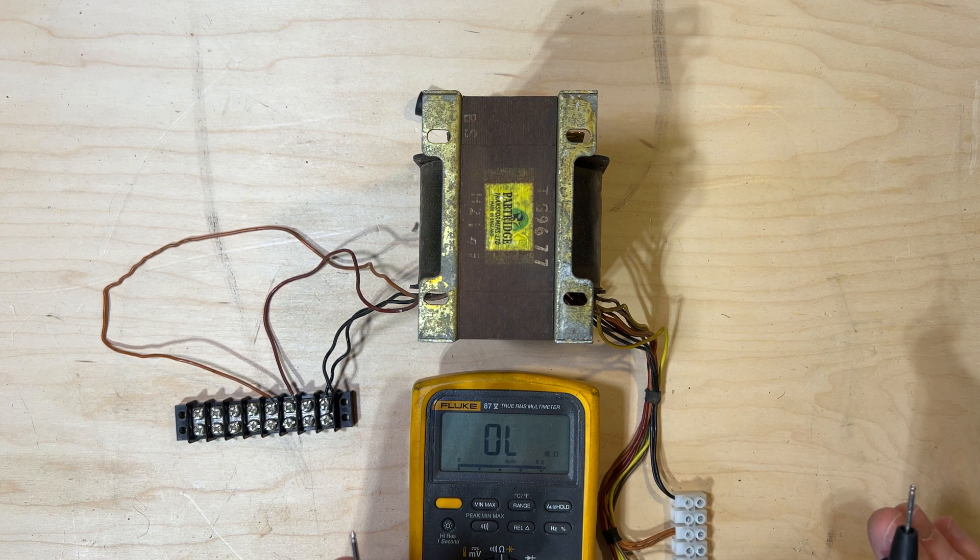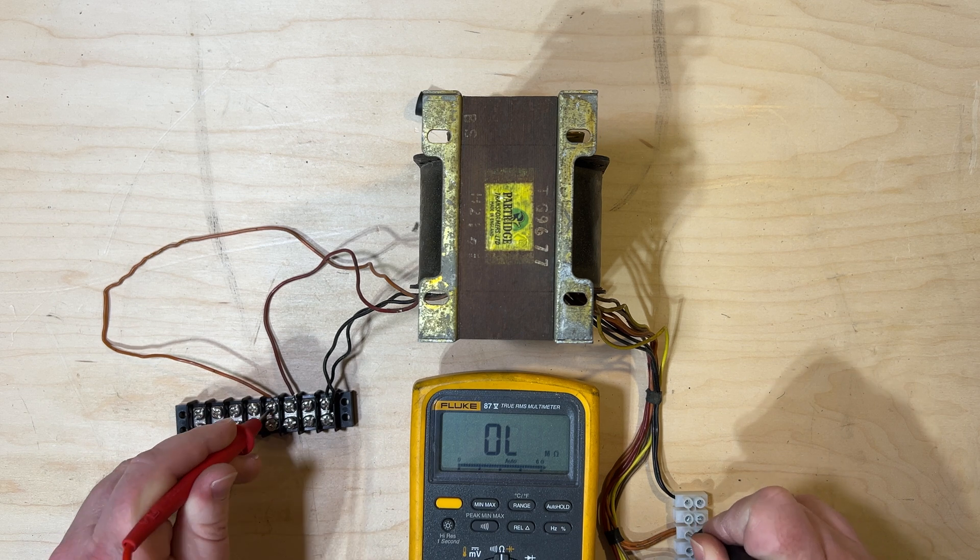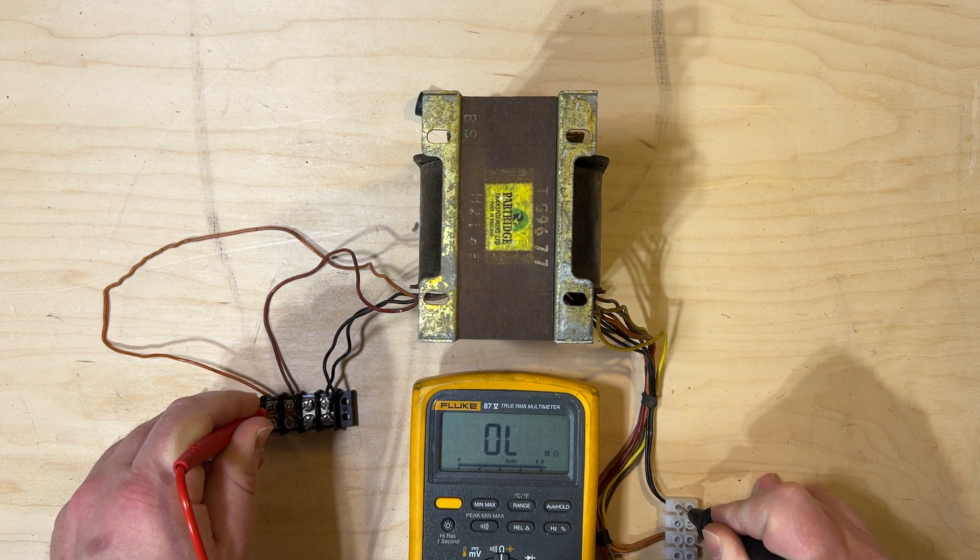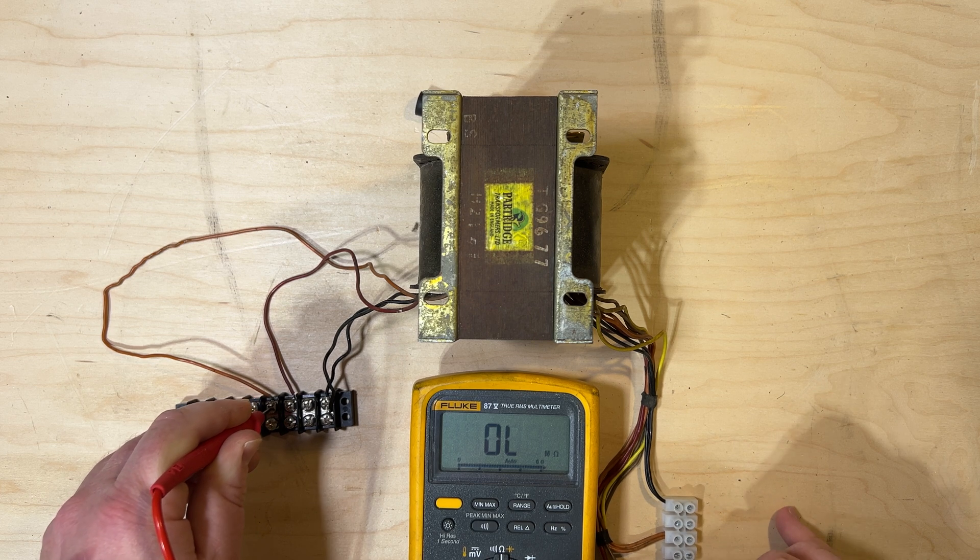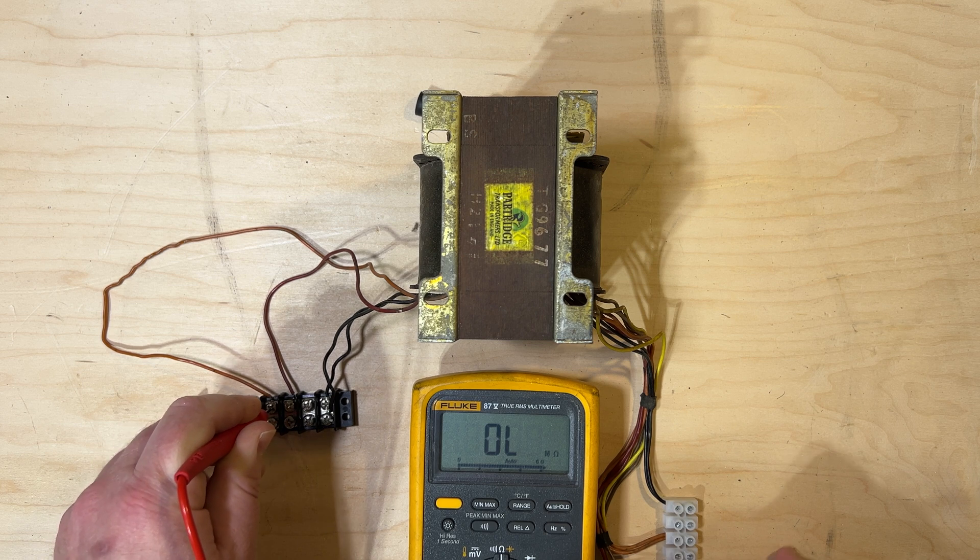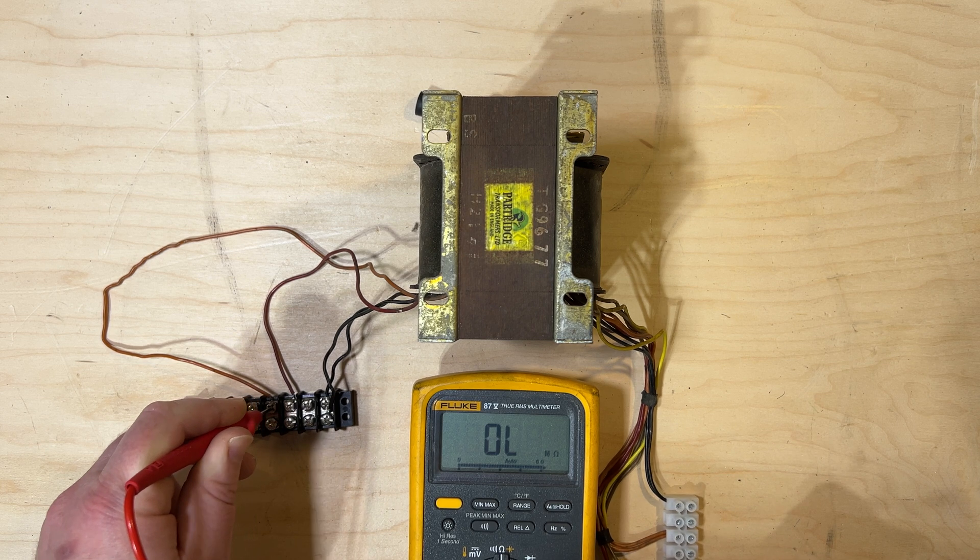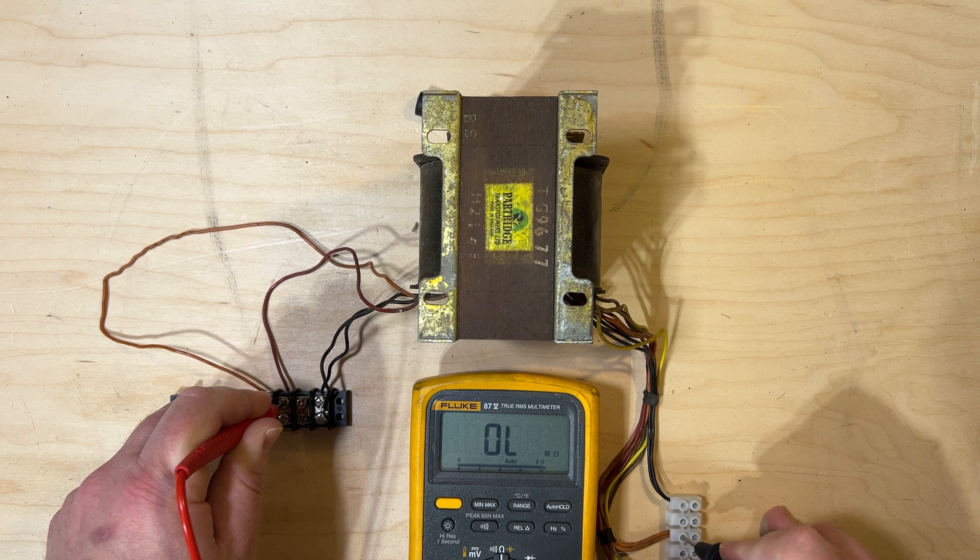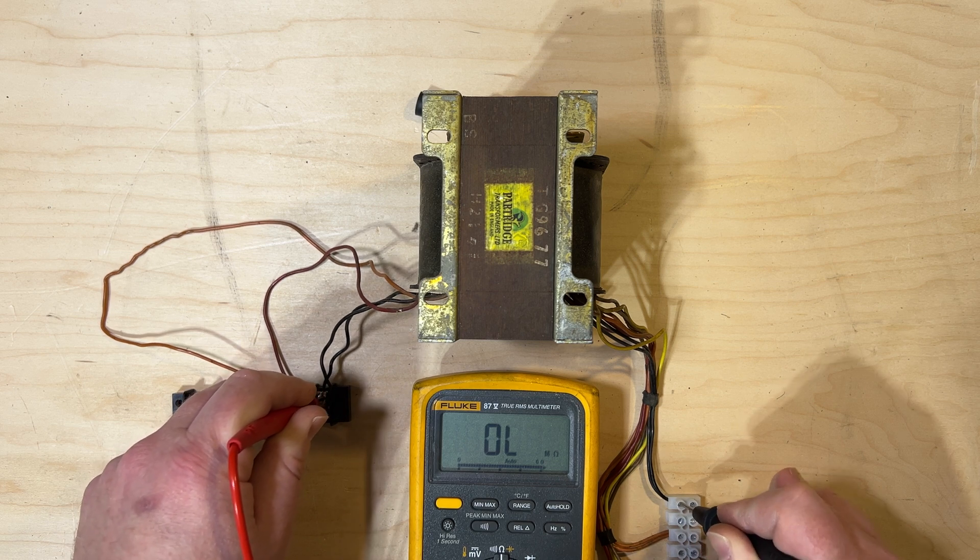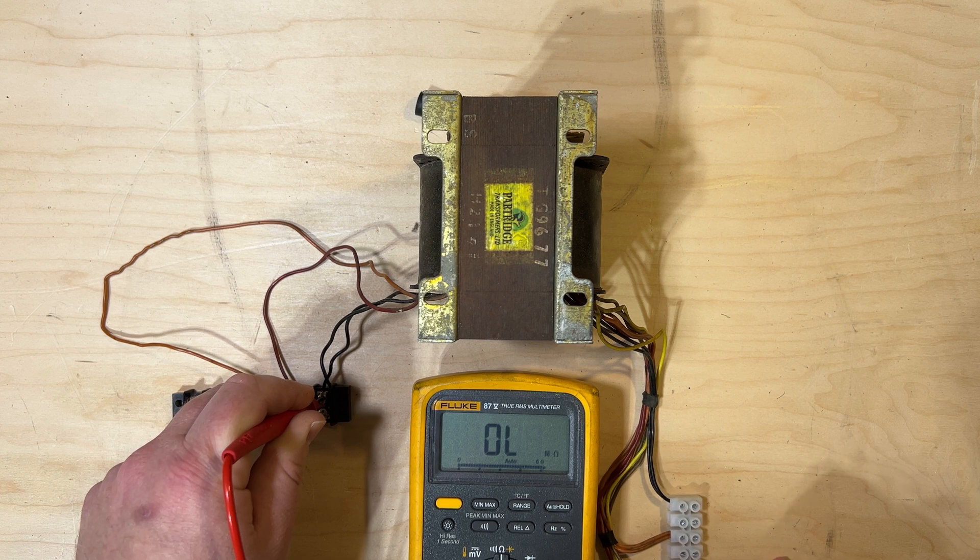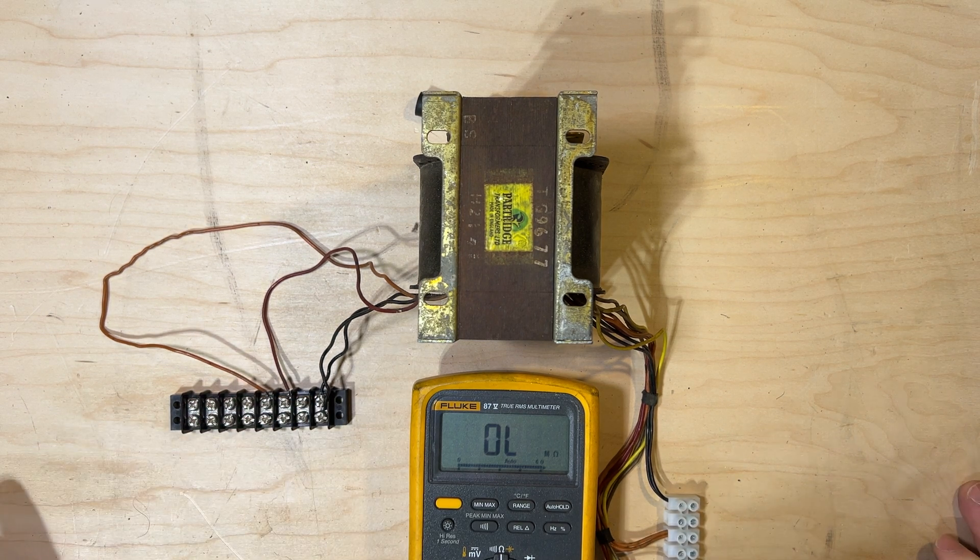Now, the important thing here that we want to test for, is that we don't have a connection between our primary and our secondary anywhere. If we did, that would show that we have a short circuit to the coil or to the outer casing from either the primary or the secondary. So, you actually really want to make sure you test this. Make sure nothing is connected from primary to secondary before applying any voltage. Because that's going to let the magic smoke out if you do. And there's no putting that back in.